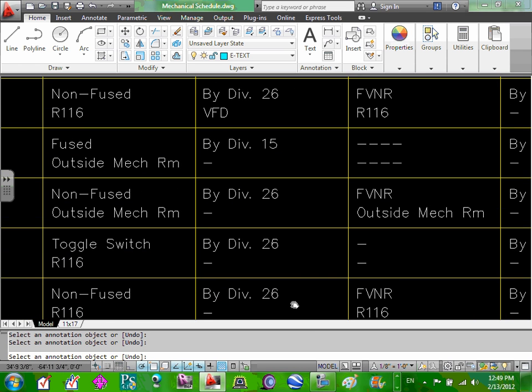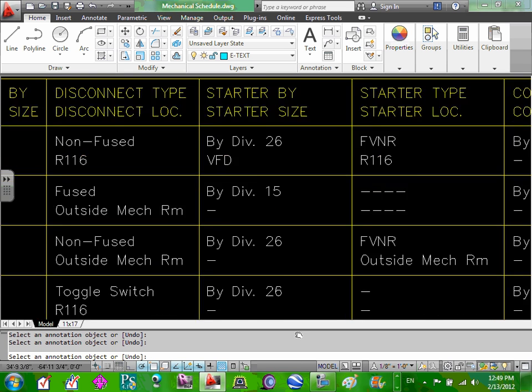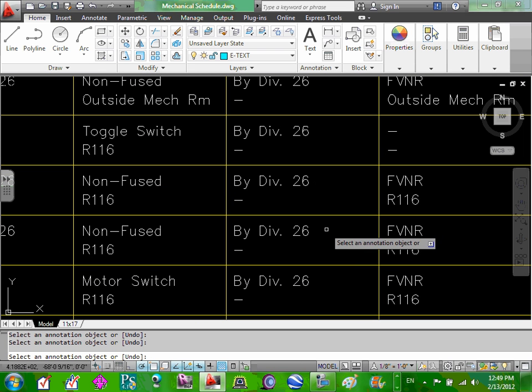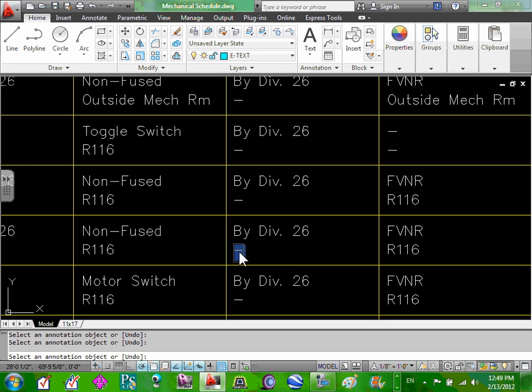Let's go to, what's this one? This is the starter, by starter type. Now we start. The starter by division 26, the starter size, it's going to be NEMA. Now, I want you guys to go from here to the NEMA, and this is how you size a NEMA. You're going to go to page 6-4, and it's a 208 system, and I need 2 horsepower. So what's the NEMA that gives me 2 horsepower? Go all the way to the first column, the NEMA size, 0. So I need NEMA 0. Everybody got that one?